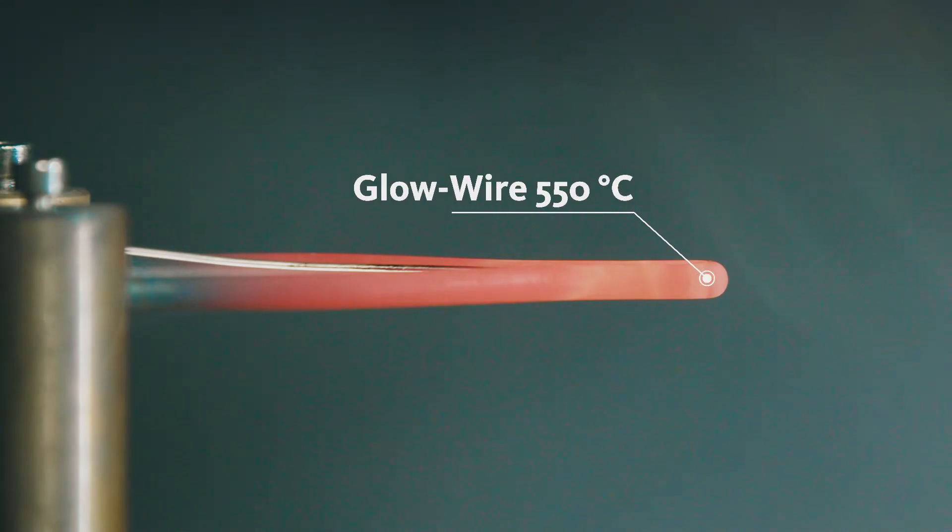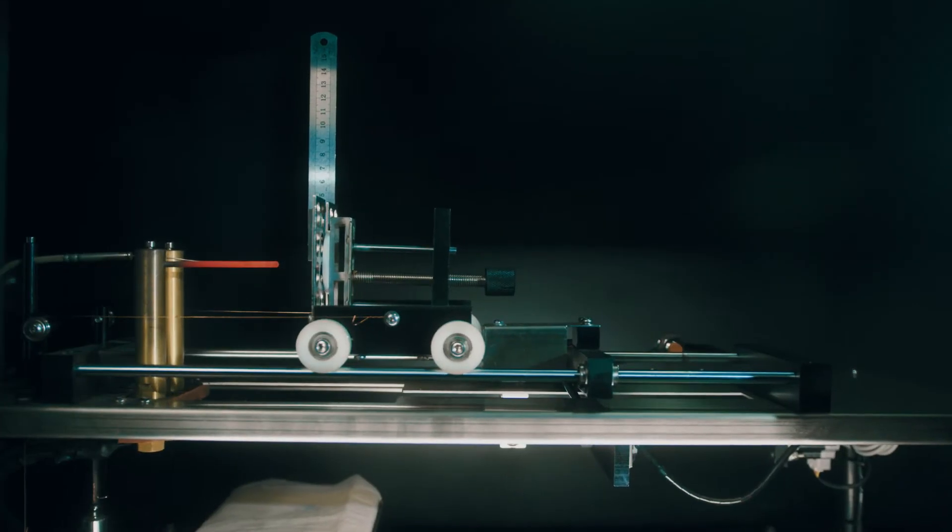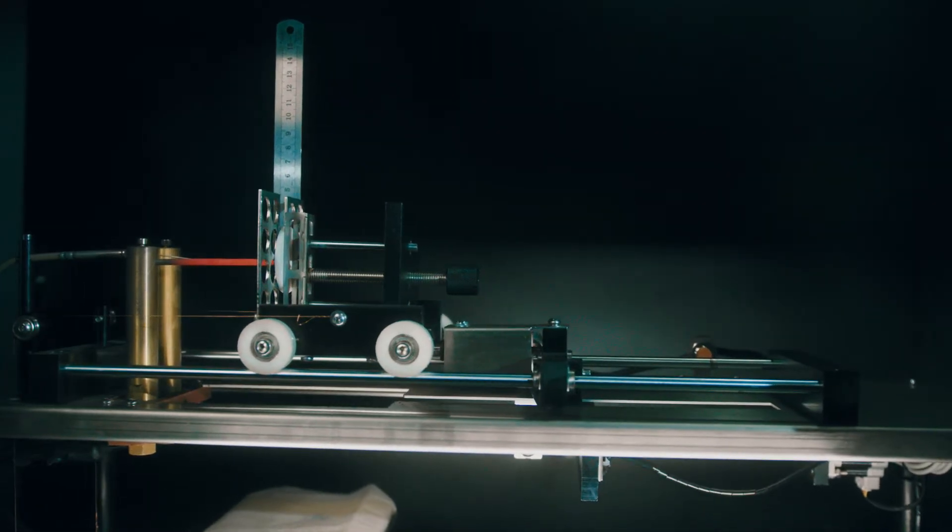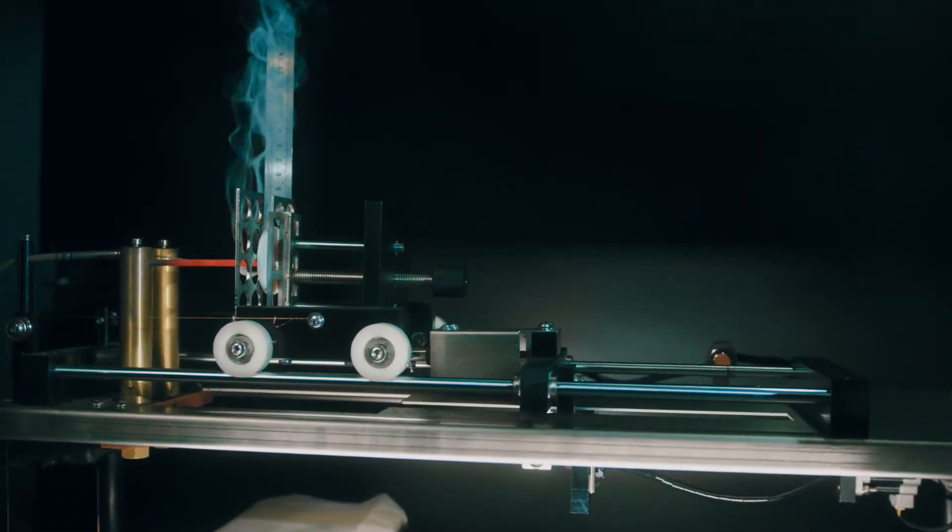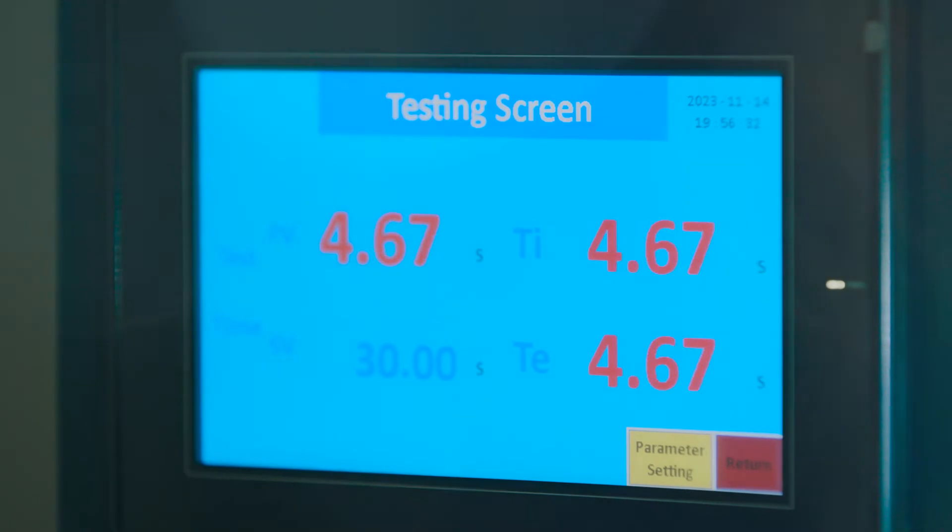The temperature of the normed glow wire is 550 degrees Celsius. The glow wire is applied for a duration of 30 seconds.